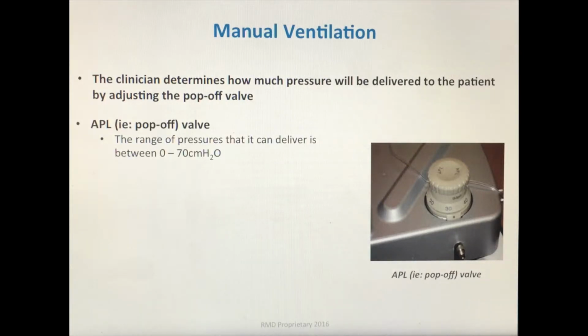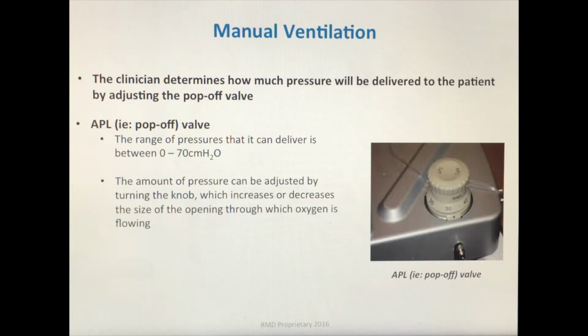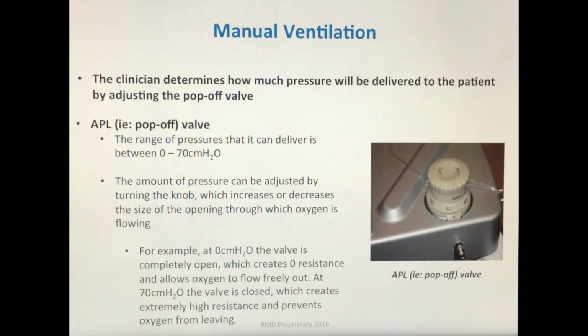The range of the pop-off valve is between 0 and 70 centimeters of water pressure. You can change the resistance, or change the pressure, by adjusting or turning the pop-off valve. At 0 centimeters of water pressure, that valve is completely open, which means the patient is breathing against no resistance, and therefore no pressure will be built up. At 70 centimeters of water pressure, that valve is now completely closed. So the patient is breathing out against something that will not let them breathe out because it's closed. Therefore, the pressure will continue to rise.